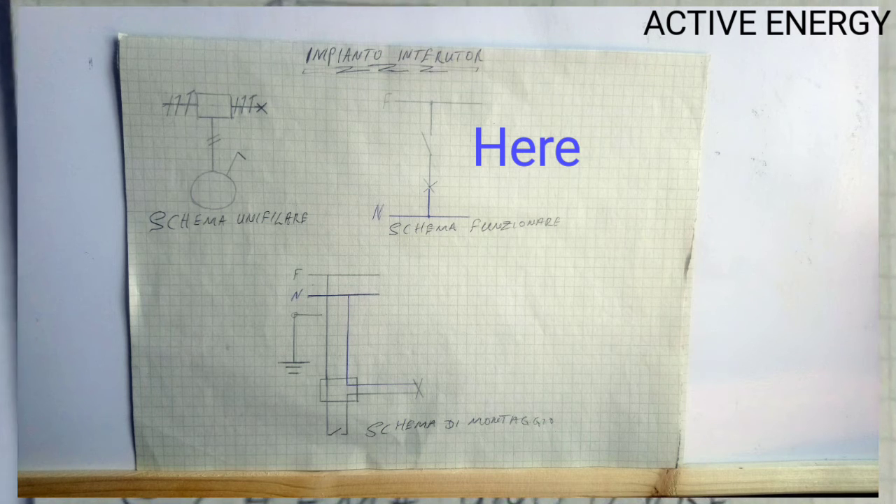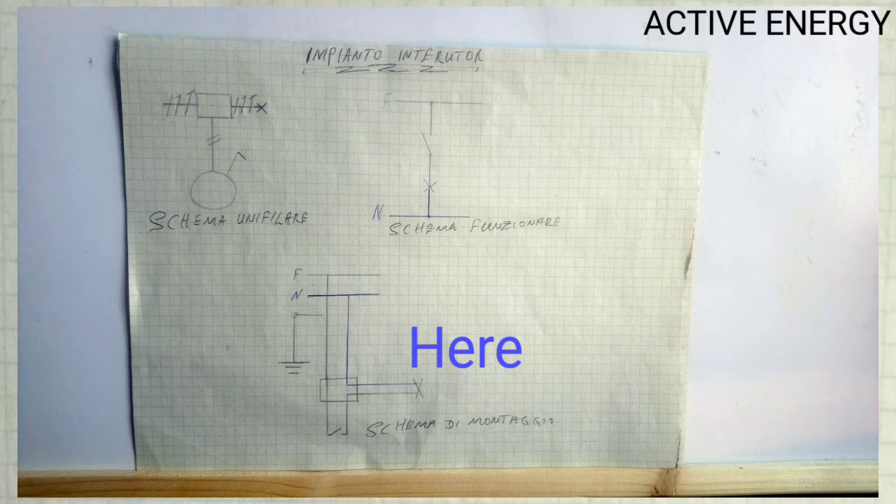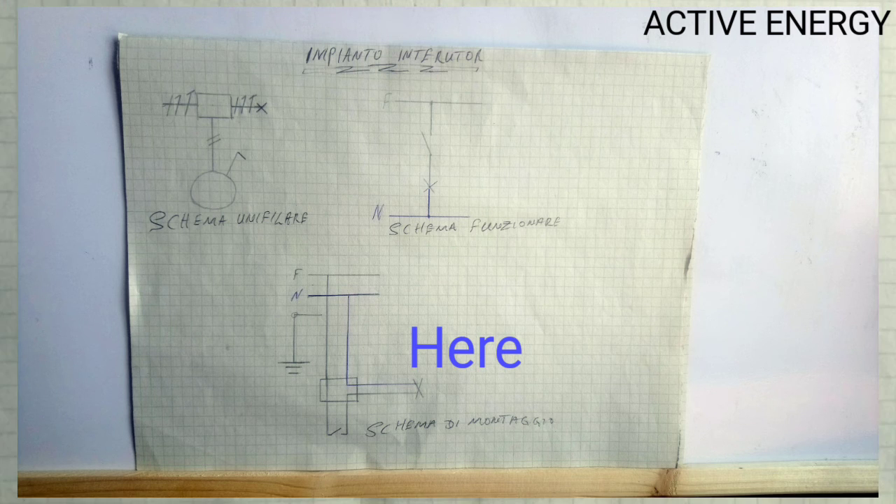Then in the Schema di Montaggio, that is the mounting diagram — the complete full diagram. Here you have the ground wire, which passes through the junction box. Then you have the junction box, and the phase wire goes directly to the switch. From the switch, you have the return wire that goes through the junction box to the lamp. Then from the lamp, you see the neutral wire that goes directly to the source.